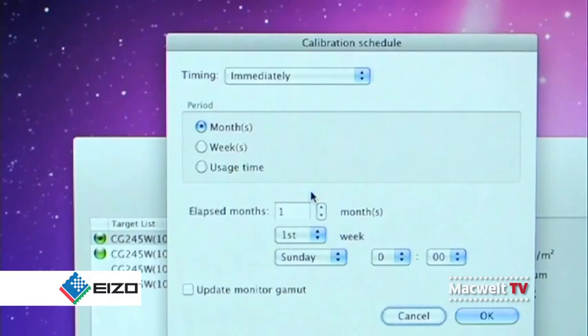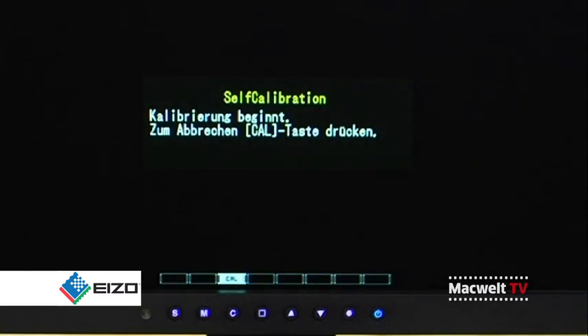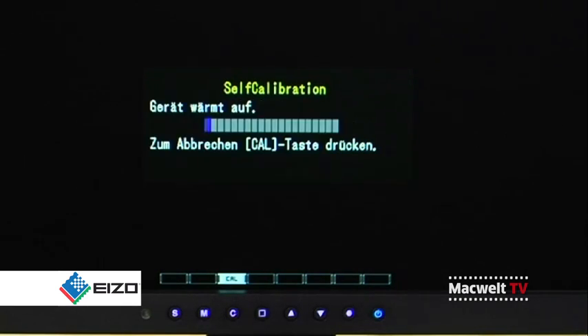Finally, you can set the time at which the monitor should switch itself on and calibrate. For example, every Sunday at midnight. As soon as that time is reached, the device switches itself on, warms up for a few minutes, and begins the calibration. The computer can stay switched off while this is happening. From now on, you won't need to carry out a manual calibration more than once a year.